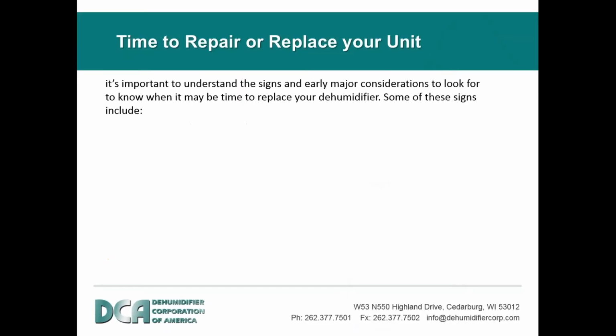In the meantime, it's important to understand the signs and early major considerations to look for to know when it is time to replace or repair your dehumidifier. Some of these include experiencing more than 1 or 2 service calls per year. And by these, I mean over and above the normal service that's required, and that would be maintaining the return air filters and adjusting the tension on the belt, and that should be done twice a year, along with at least once a year, checking all the electrical connections to make sure they're all tight.